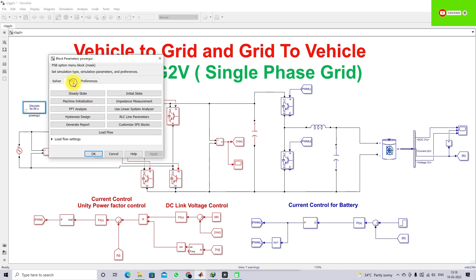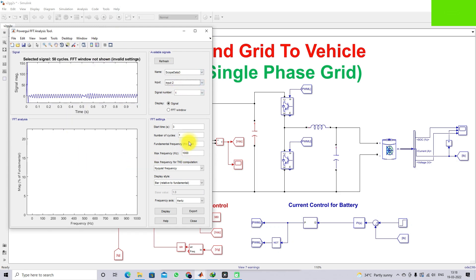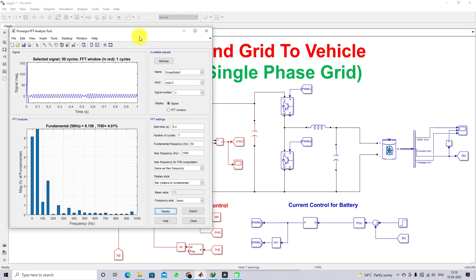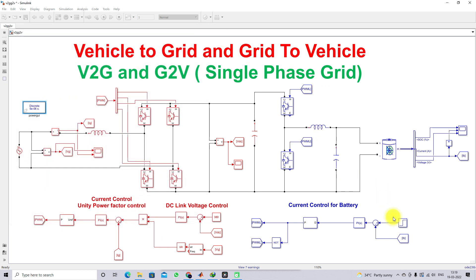Next, we check the THD of the source current during charging and discharging. I use a 0.3-second window to measure the THD. During discharging, the THD is around 4%, which is less than 5% and meets the IEEE standard. During the recharging condition, the THD is around 3.7%, which is also less than 5% and meets the IEEE standard.